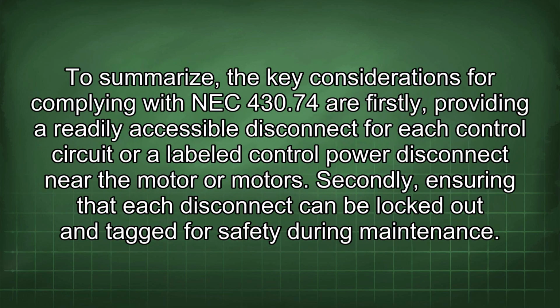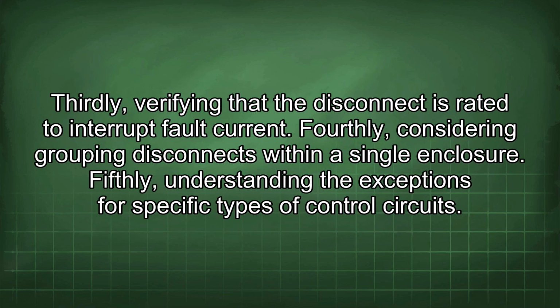To summarize, the key considerations for complying with NEC 430.74 are, firstly, providing a readily accessible disconnect for each control circuit or a labeled control power disconnect near the motor or motors. Secondly, ensuring that each disconnect can be locked out and tagged for safety during maintenance. Thirdly, verifying that the disconnect is rated to interrupt fault current. Fourthly, considering grouping disconnects within a single enclosure. Fifthly, understanding the exceptions for specific types of control circuits.